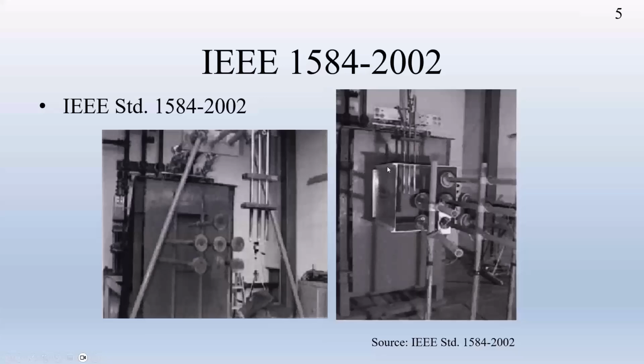This is a vertical electrode inside the box, and these are the calorimeters that try to measure the incident energy. The other configuration is the vertical electrode in the open air. From a calculation point of view, that is a relatively simple configuration. Everybody can look at the setup in the field and identify what kind of configuration it is. So at that time, we only identified and provided the formula for two configurations.